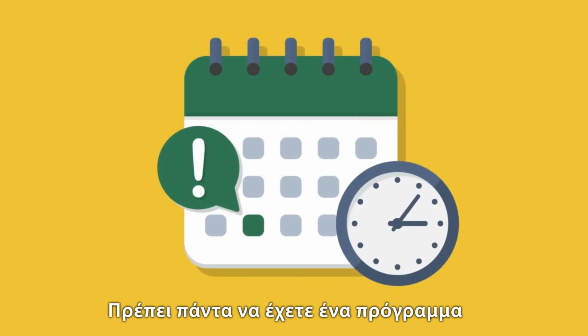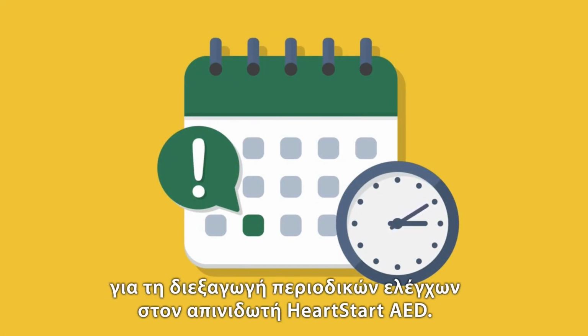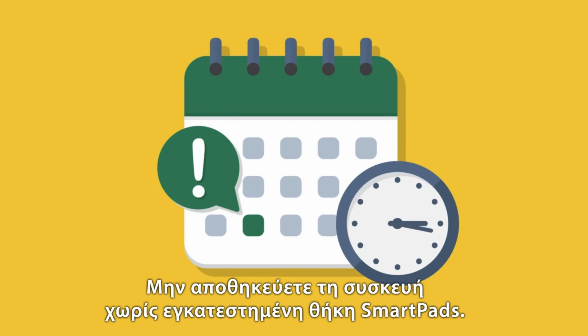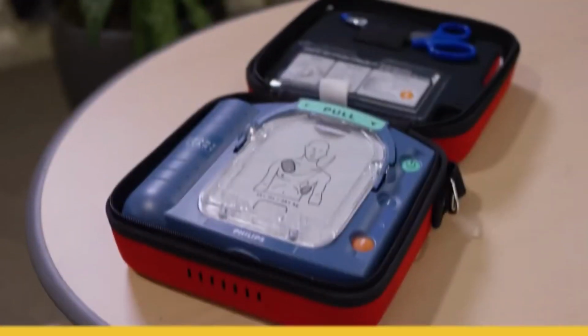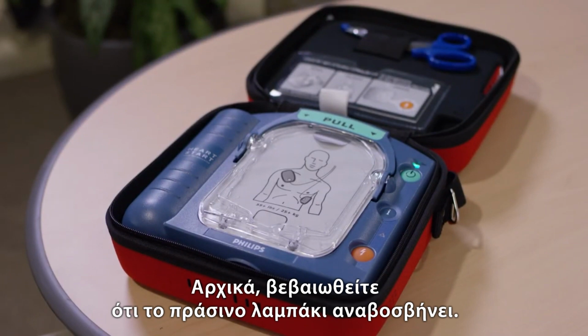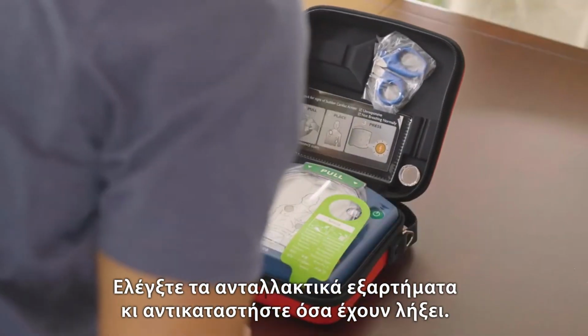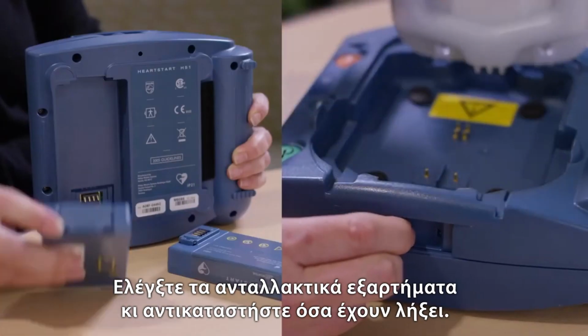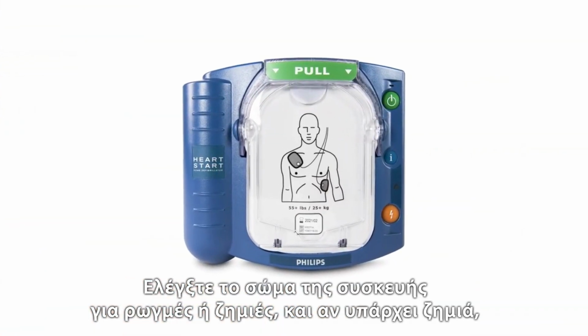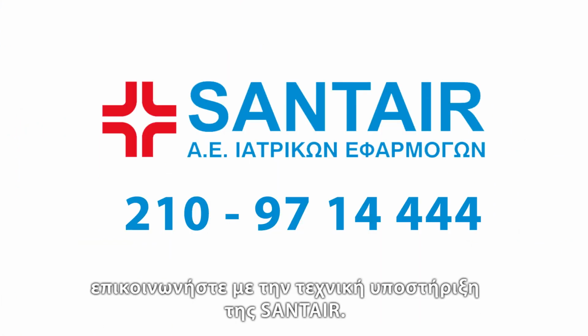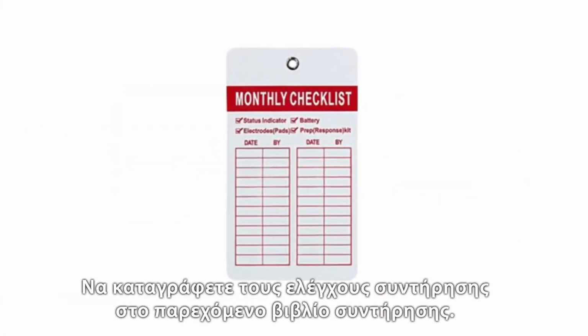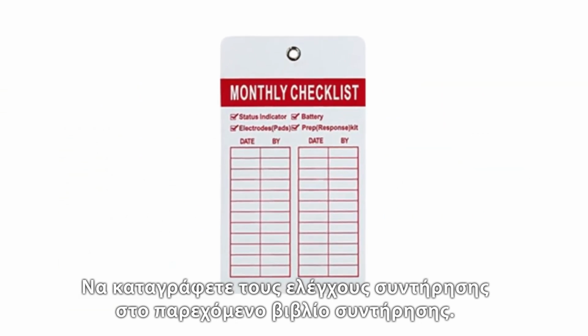You should always establish a schedule for performing periodic checks to the Heart Start Home AED. Don't store the device without a smart pads cartridge installed. First, make sure that the green ready light is blinking. Check any spare accessories for damage, and replace any that have expired. Inspect the body of the unit for cracks or damage, and if damage is present, contact Philips technical support for assistance. You should record all maintenance checks in the included maintenance log.